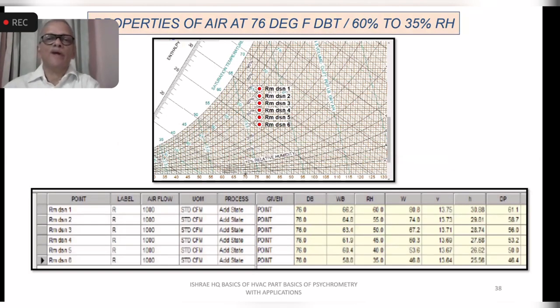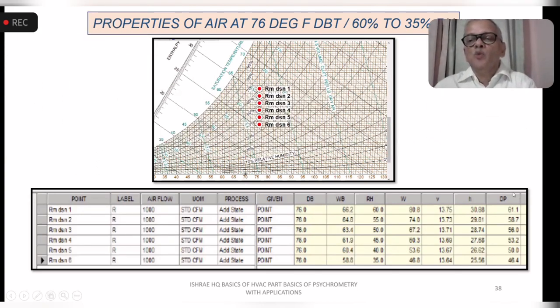Now, this is taken from the software. For the room design conditions 1 to 6, I have selected the same dry bulb temperature, but the relative humidity is different. So here you see room designs 1, 2, 3, 4, 5, 6. It tells you the dry bulb temperature is 76 throughout, and the relative humidity is coming down from 60, 55, 50. So you see the relative humidity values here. Then you will see the dew point temperature. This corresponds to the moisture content. You go horizontally to the saturation line. So that is the DP line which we had seen in the previous skeleton charts.